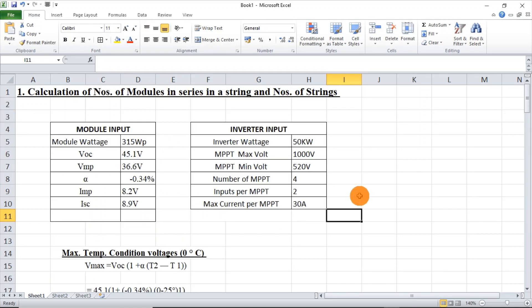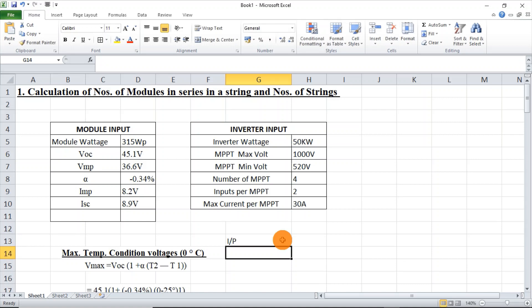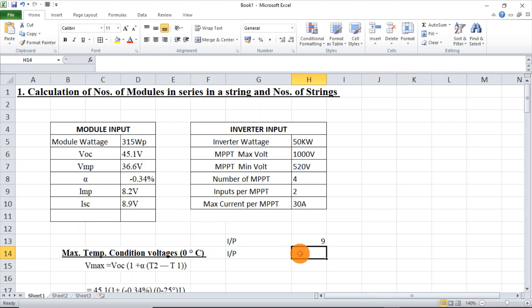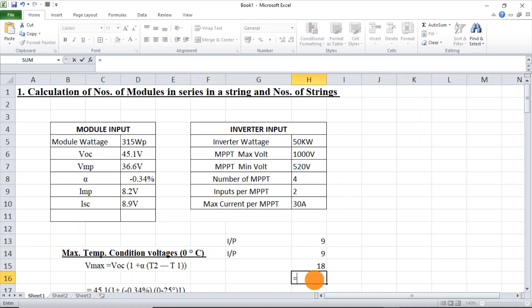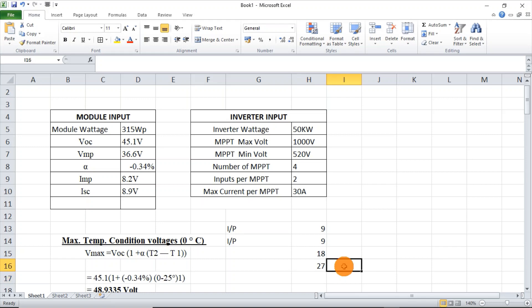Now regarding paralleling strings: we need to check the current per MPPT. Taking input 1 and input 2, each has a short circuit current of 9A, so together that is 18A flowing into the MPPT. Applying a safety factor of 1.5 times, that comes to 27A. Since our inverter allows only 30A per MPPT, we can connect only one string per input — we cannot parallel strings in this inverter.